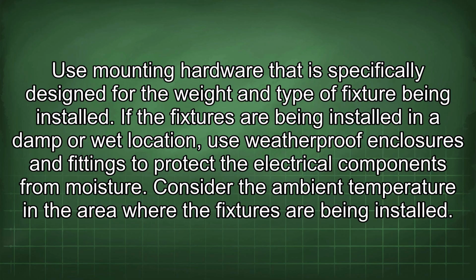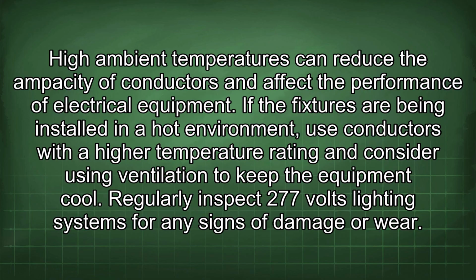If the fixtures are being installed in a damp or wet location, use weatherproof enclosures and fittings to protect the electrical components from moisture. Consider the ambient temperature in the area where the fixtures are being installed. High ambient temperatures can reduce the ampacity of conductors and affect the performance of electrical equipment. If the fixtures are being installed in a hot environment, use conductors with a higher temperature rating and consider using ventilation to keep the equipment cool.